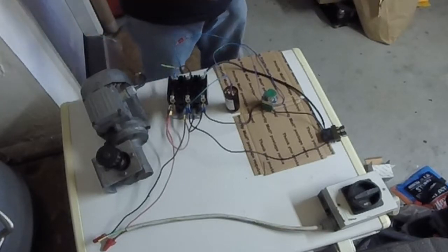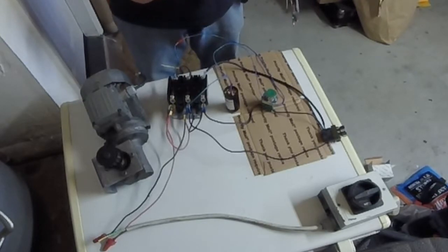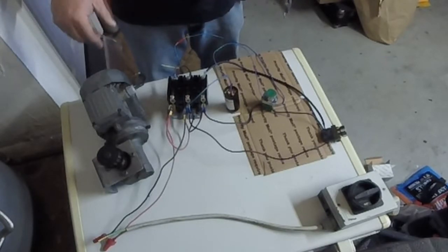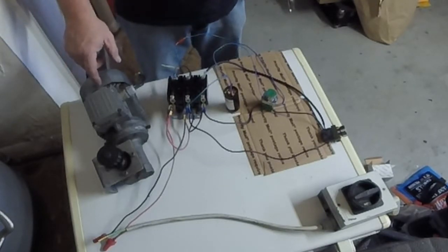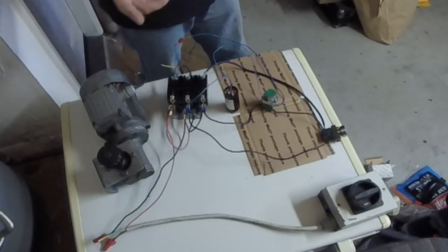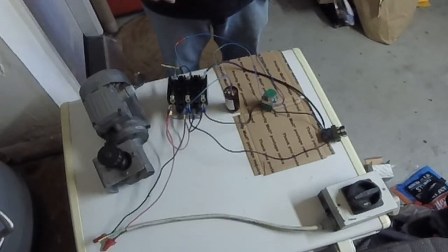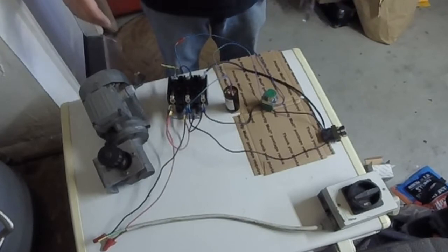For this small of a motor, I just put like 40 microfarads to it. Big motors, you know, seven and a half horsepower, 10 horsepower motor, you're probably going to have to have an excess of 500 to 600 microfarads of capacitance to get one of those fired off. But these little motors, I think this one's probably not even a half horsepower. 20 microfarads would probably get this motor fired off. But this was the first capacitor that I grabbed out of the stack and it's within the range.